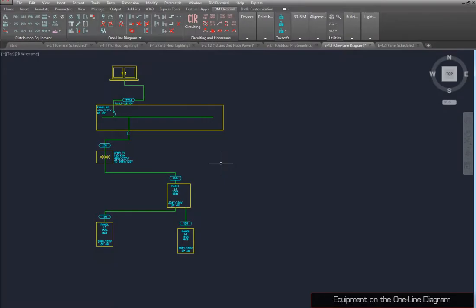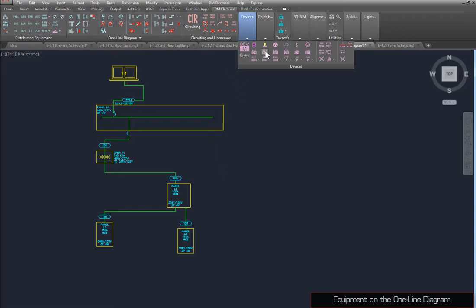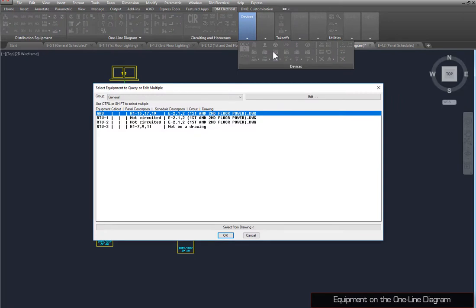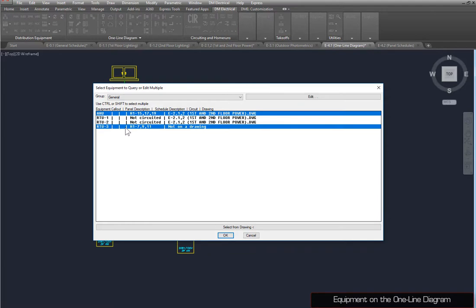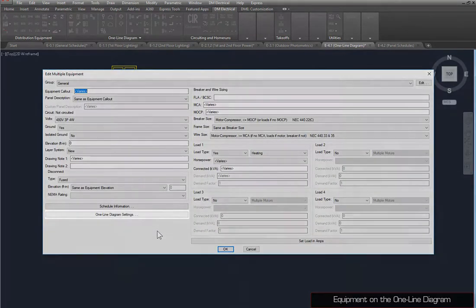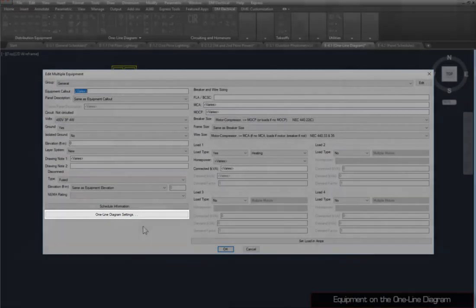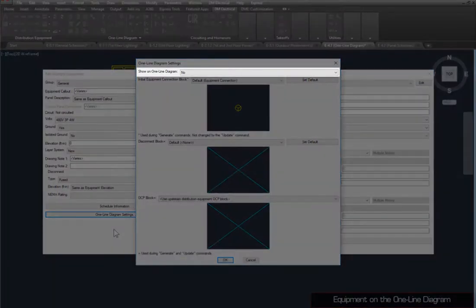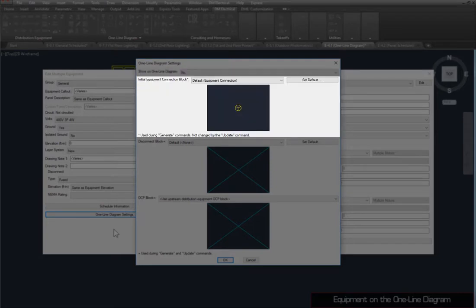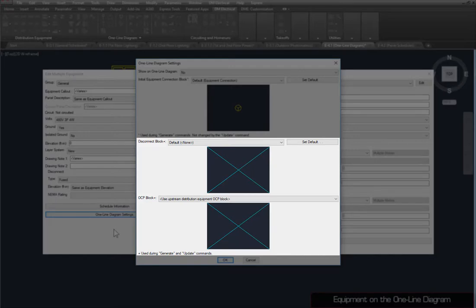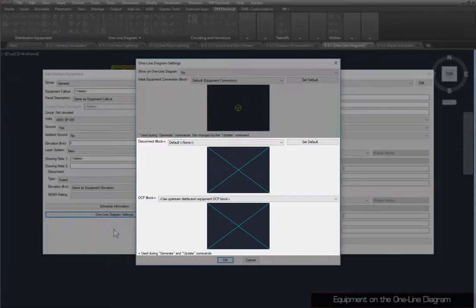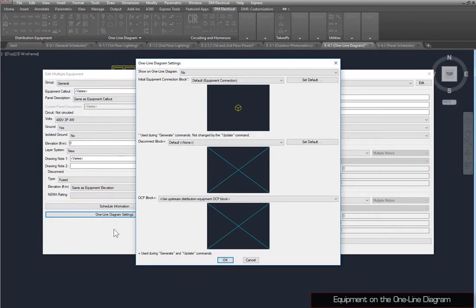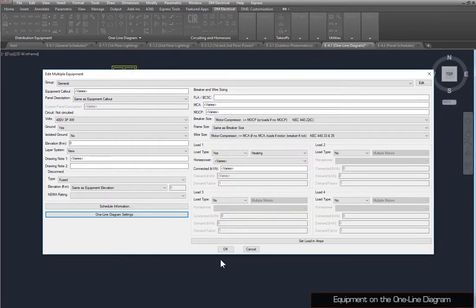Equipment connections can be shown in the one-line diagram, which we covered in Part 3. First, we'll use the Query or Edit Multiple Equipment command to make changes to the equipment. Select AHU and RTU3 to edit, then press the One Line Diagram Settings button. Here, you can set whether the equipment is shown on the one-line diagram, the block used to represent the equipment, and the disconnect and overcurrent protection blocks shown on the branch circuit. Set Show on one-line diagram to Yes, press the OK button, and press the OK button again to save the changes.